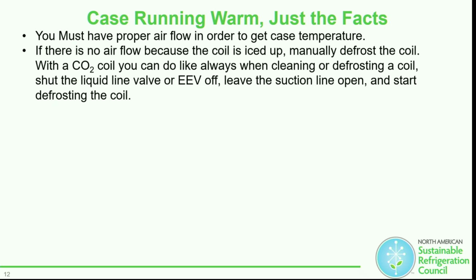When cleaning or defrosting a coil, shut down the liquid line or the EEV, leave the suction line open, and start defrosting the coil. Before you start touching any cases, especially since we're talking about CO2, double, triple check the check valves inside those cases. There's a certain percentage, I think about 20%, if you talk to any construction person, they'll tell you that a lot of times 20% of them usually get done on a Friday or Monday. So during construction, if they don't check it, you might have some that are backwards, and that's a safety hazard for you, especially if you're not paying attention.